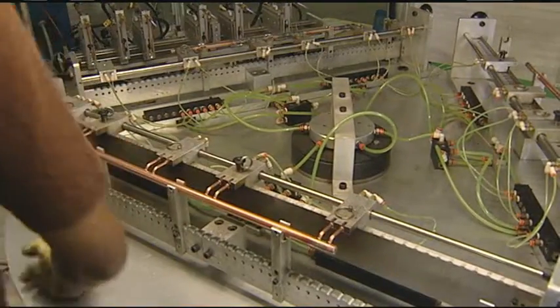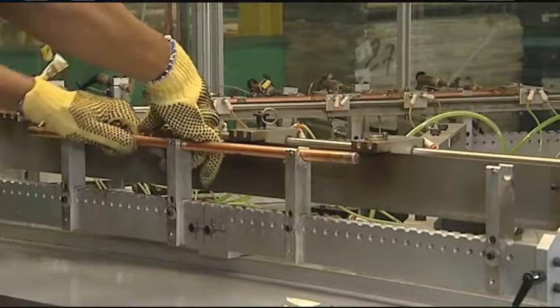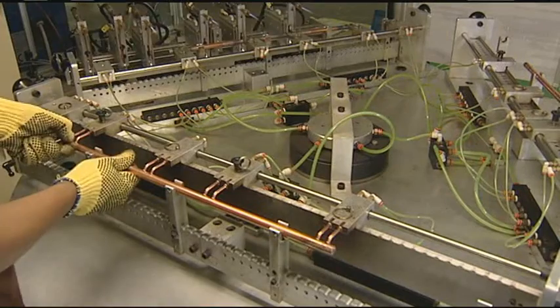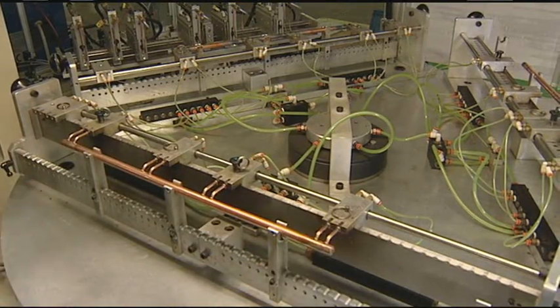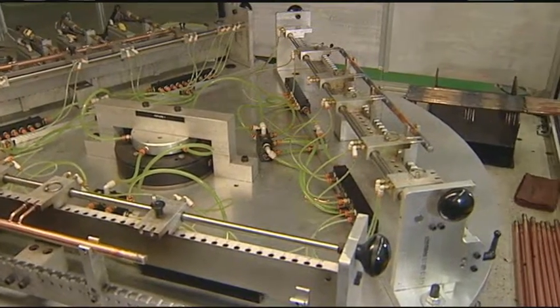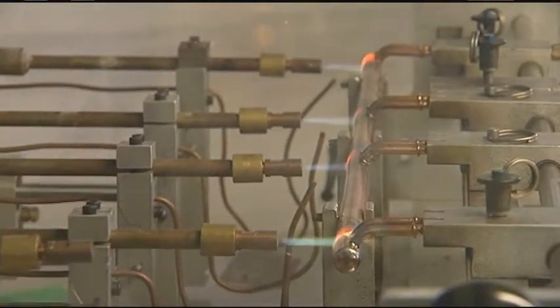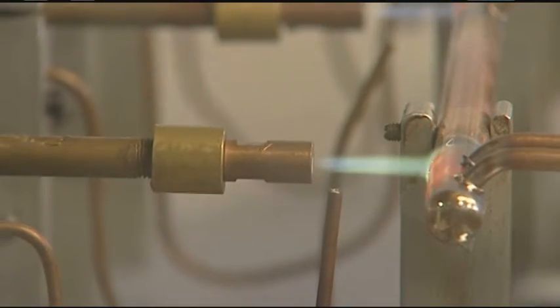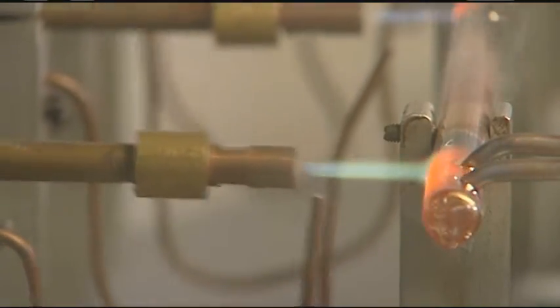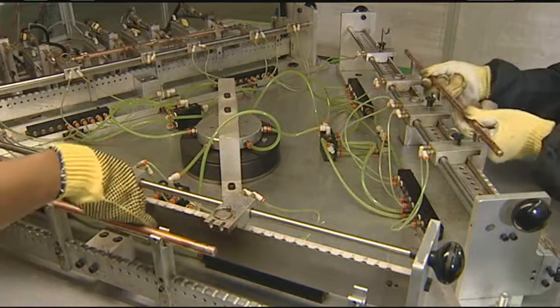Earlier we talked about the 5mm tubing and the precision required in the manufacturing processes. This machine has something to do with that process. What you're doing here is taking the manifold and putting the stems, or little feeder tubes, right onto the manifold. You can see green hoses on there — those are hydrogen purged. They purge all the copper on the inside to make sure we don't have any contamination and keep the copper clean on the inside. Once everything is installed and ready, there are small braze rings to ensure the amount of solder is always consistent. At the end, you have a perfect product — hundreds and hundreds of the same piece coming out exactly the same, taking the human element out of it. All you have to do is load into the fixture.